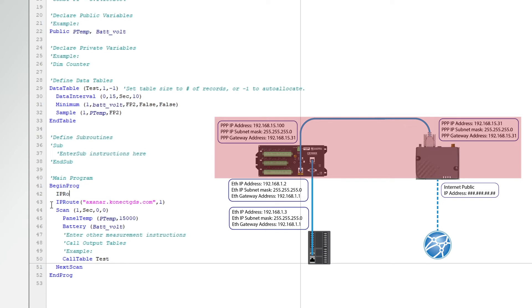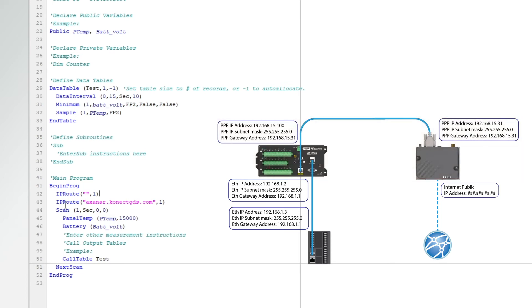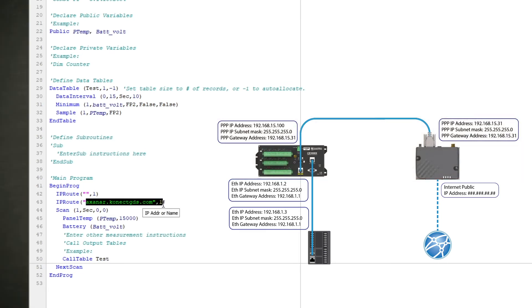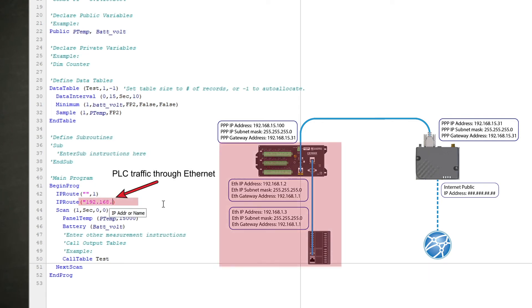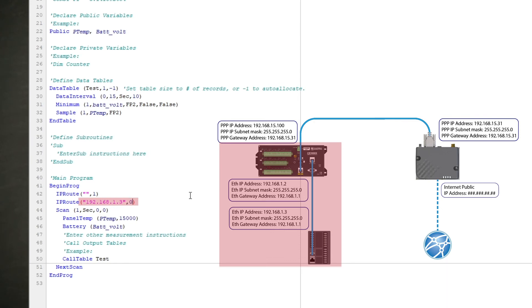Alternatively, using empty quotes for the IP address parameter will set the selected port to the default interface. Setting the second parameter to 1 sets PPP as the default interface, so all network activity will default to PPP rather than Ethernet. If this option is chosen, I will need to change the second IP route to the IP address of the PLC — 192.168.1.3 — and change the interface parameter to 0 for Ethernet, telling the datalogger to connect to the PLC through Ethernet instead of the now-default PPP interface. IP route adds a lot of flexibility for routing through specific IP interfaces.